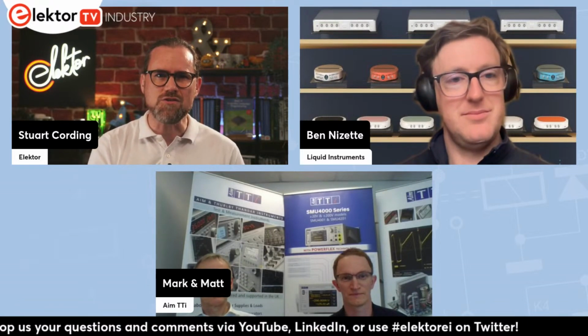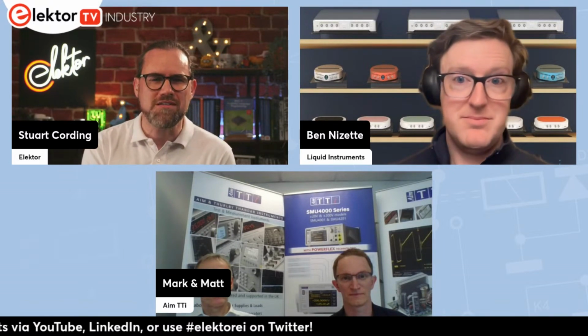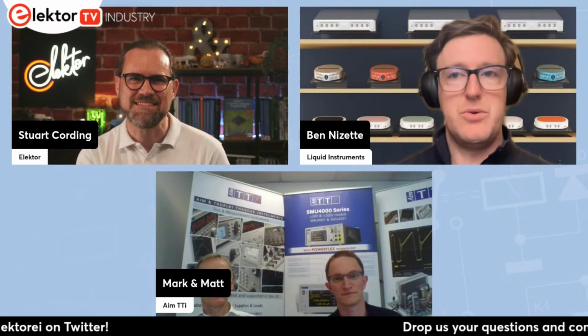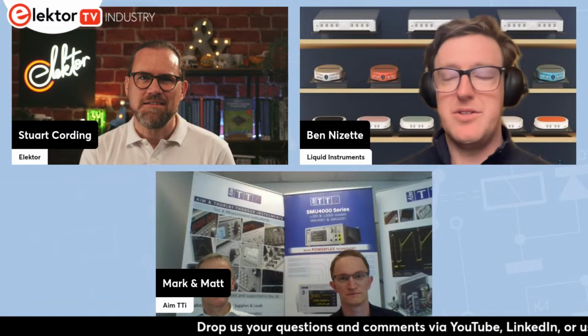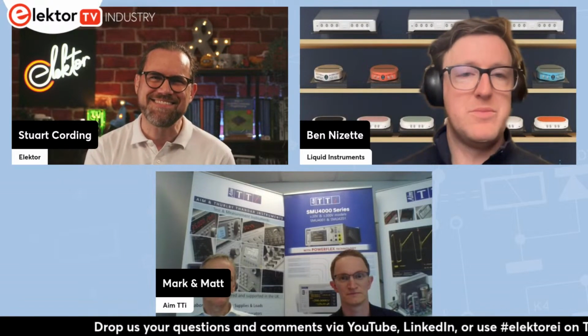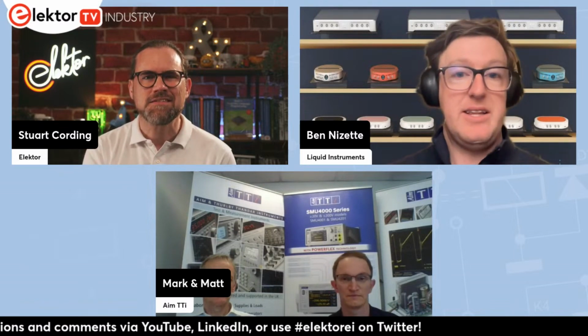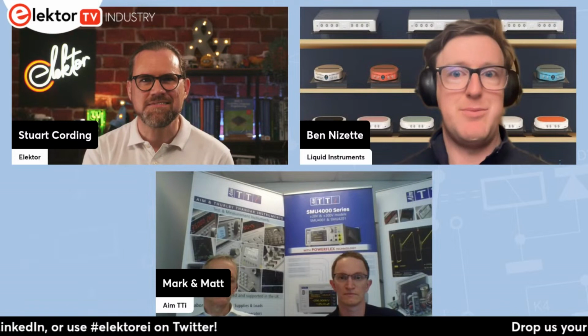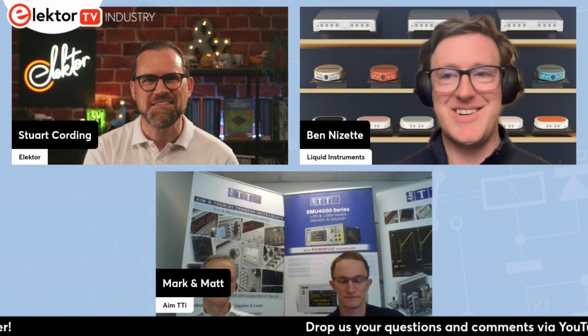What about you, Ben? Do you see an AI block for Moku on the horizon sometime? Yeah, absolutely. We've already got customers who use our Python APIs, in a testing scenario, to acquire waveforms, and then rather than putting a mask around them or trying to take a measurement out of them, they simply ask their Python-based AI model, does this look the same as my golden reference? Right. Yes or no? And that's the pass-fail criteria right there.